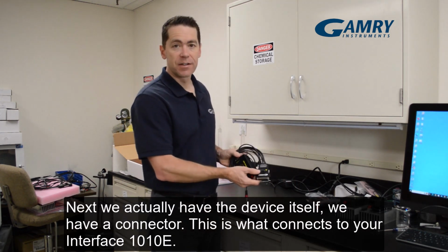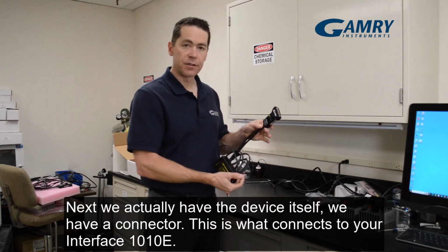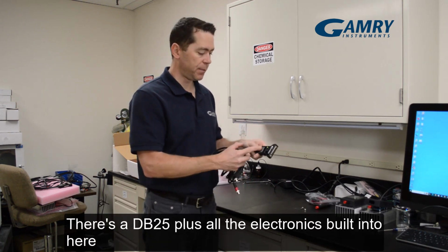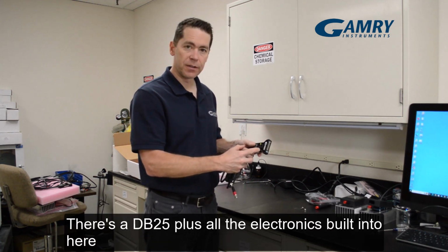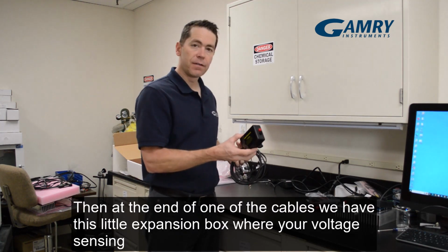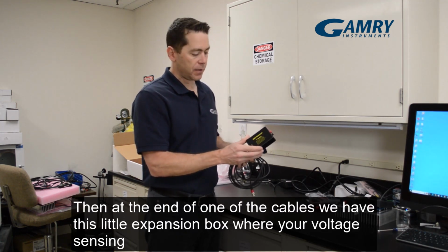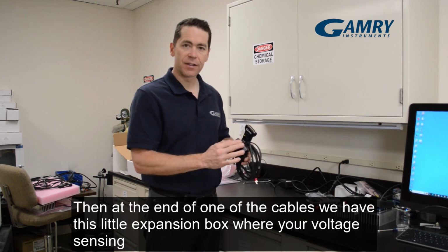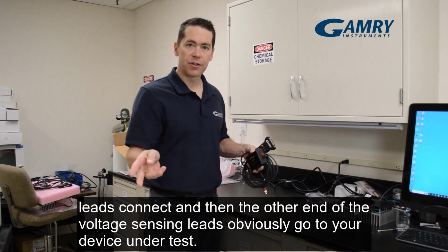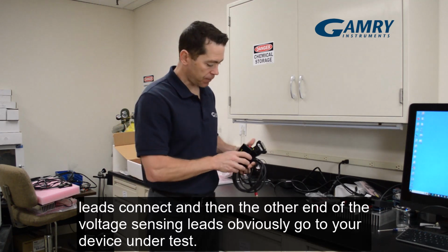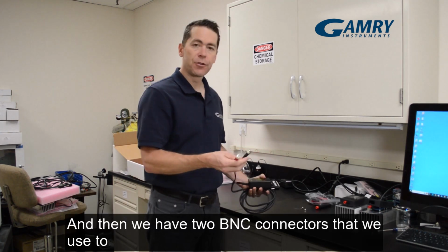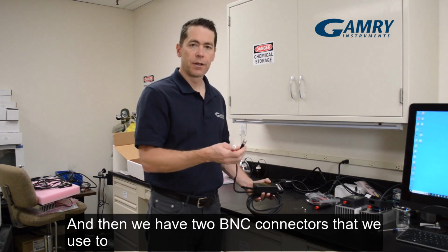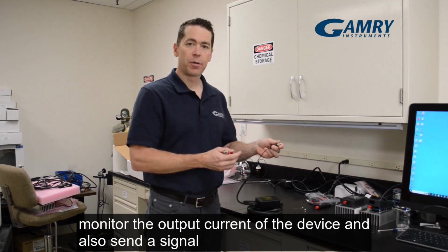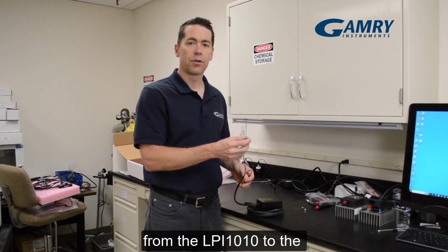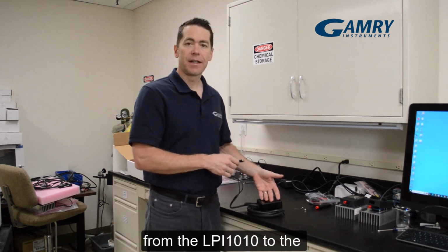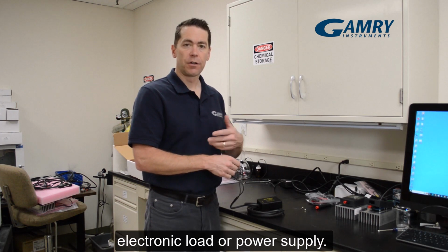Next, we actually have the device itself. We have a connector. This is what connects to your interface 1010E. There's a DB25 plus all the electronics built into here. Then at the end of one of the cables, we have this little expansion box where your voltage sensing leads connect, and then the other end of the voltage sensing leads obviously go to your device under test. And then we have two BNC connectors that we'll use to both monitor the output current of the device and also to send the signal from the LPI100 to the electronic load or the power supply.